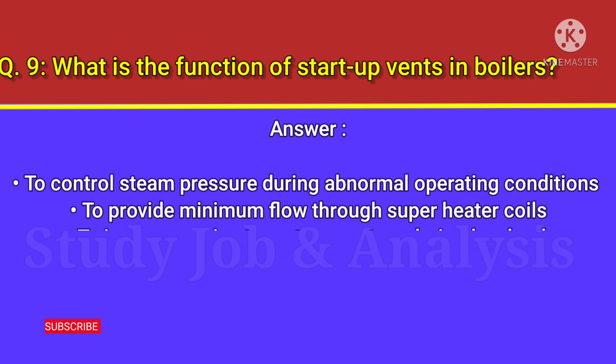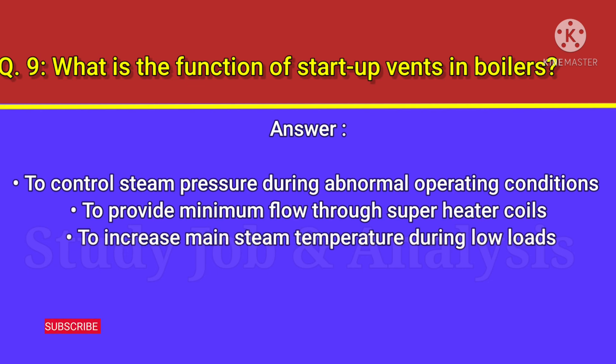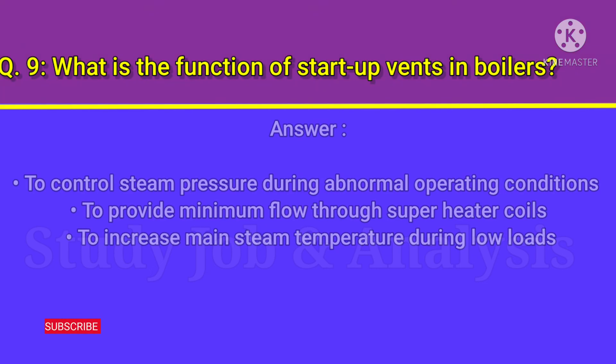Question number nine: what is the function of startup vents in boilers? Answer: To control steam pressure during abnormal operating conditions, to provide minimum flow through superheater coils, and to increase main steam temperature during low loads.